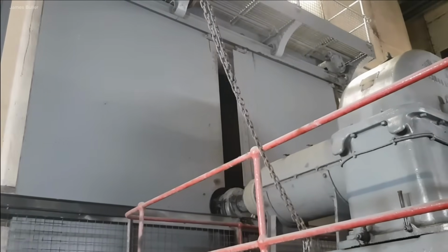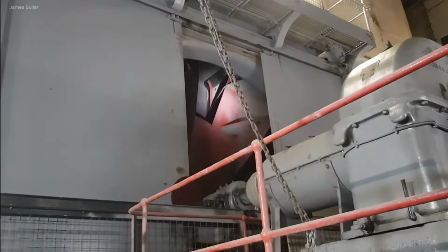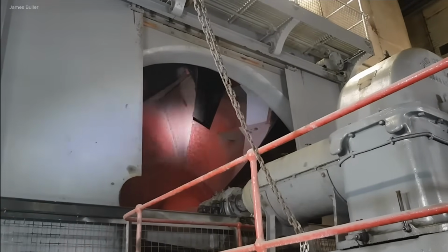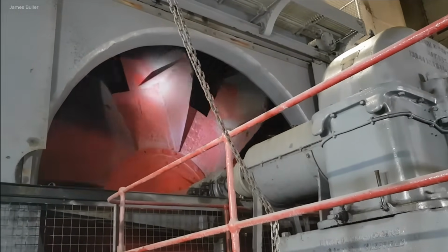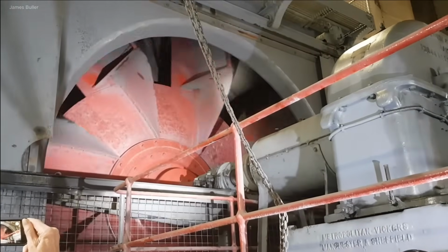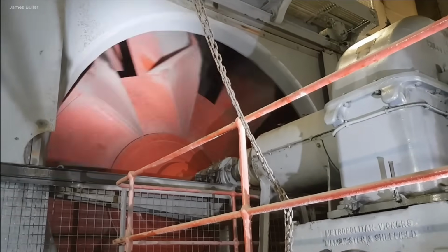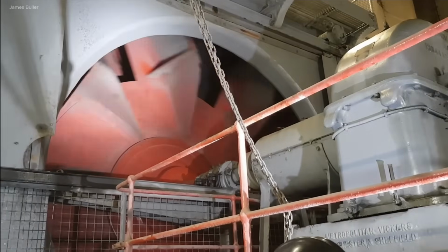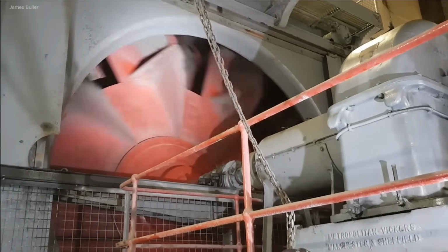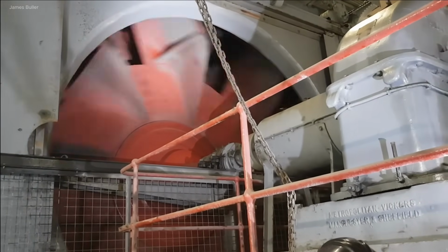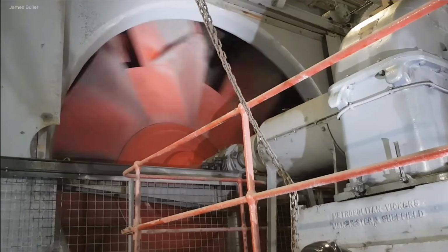The 3.8 meter tunnel fan starts up remotely via the maintenance system, activating its heat and vibration sensors. Power flows through 1 kilometer of installed cabling. As it spins, the fan circulates fresh air and is ready to reverse if needed. Its energy-efficient design supports emergency operation at 300 degrees Celsius for up to 2 hours.